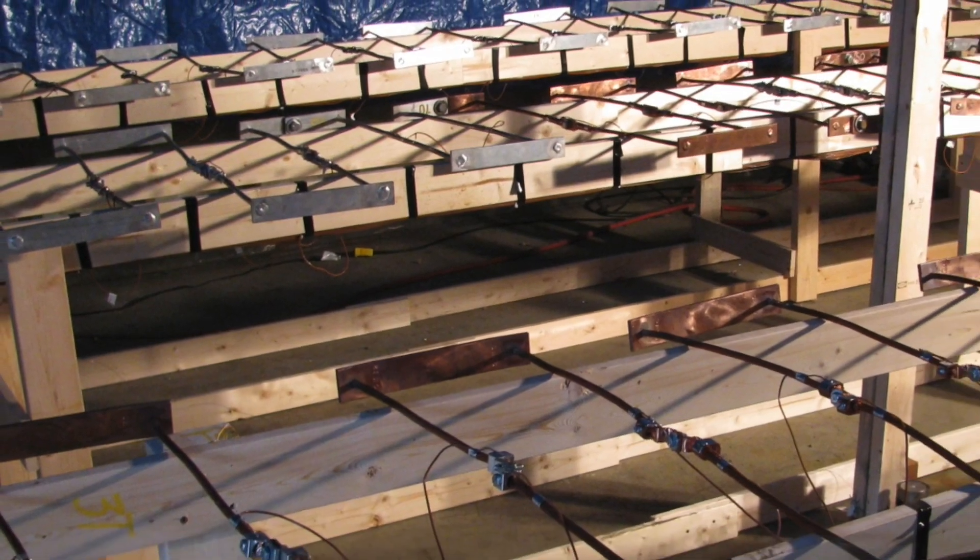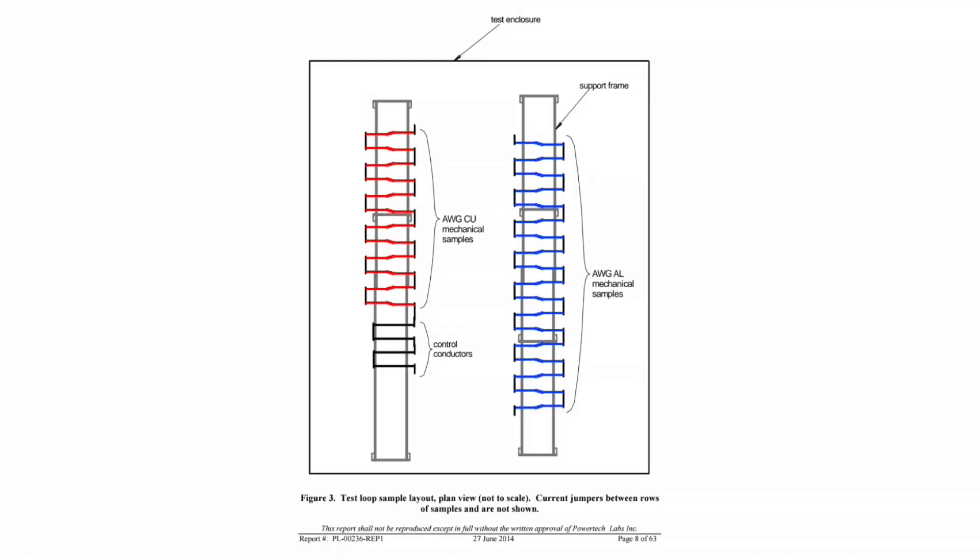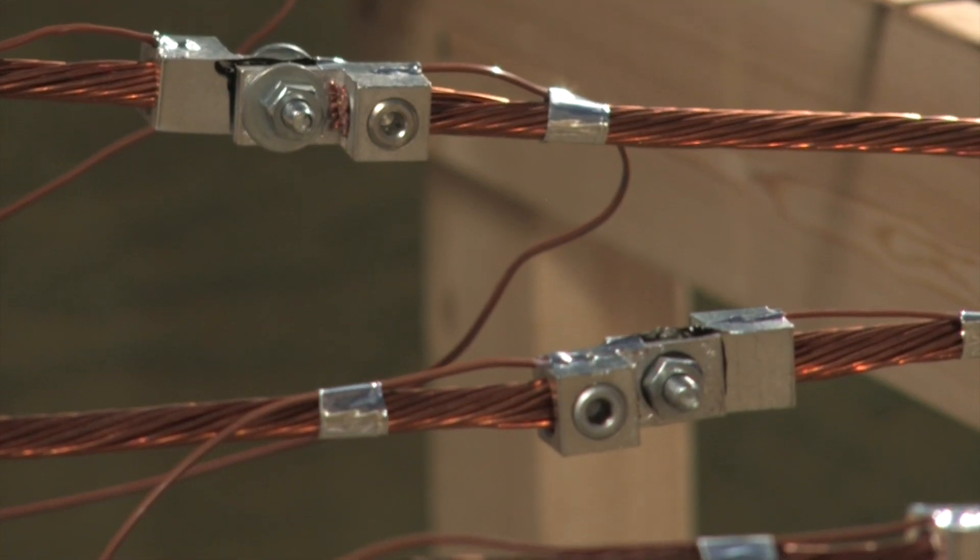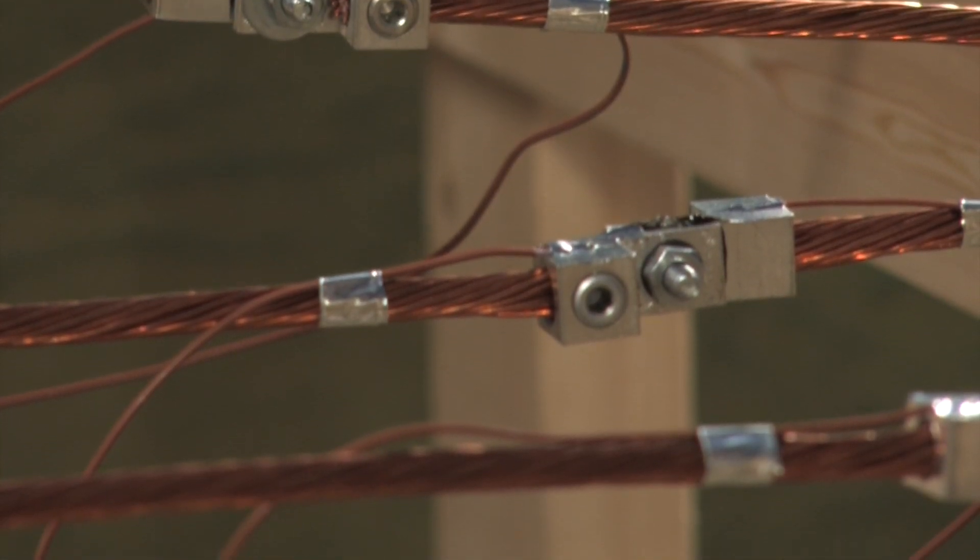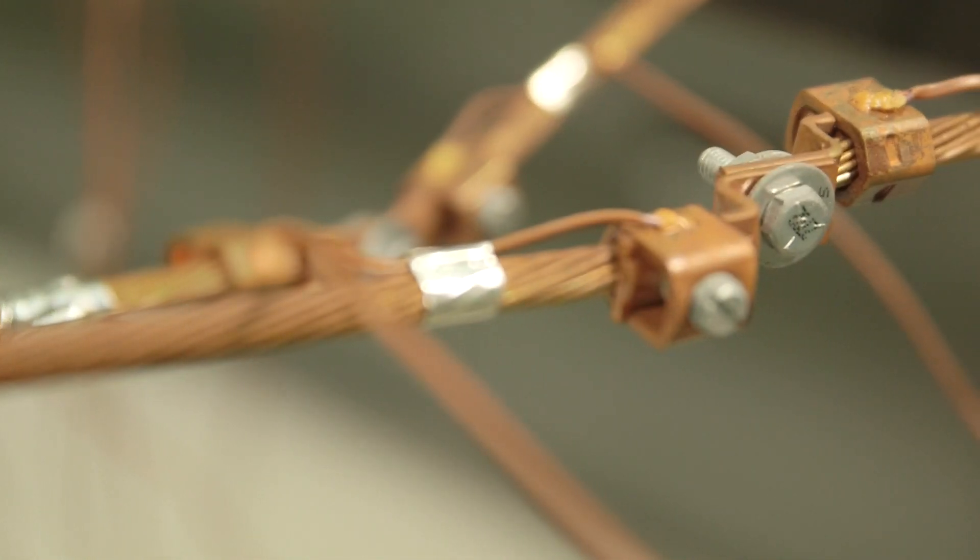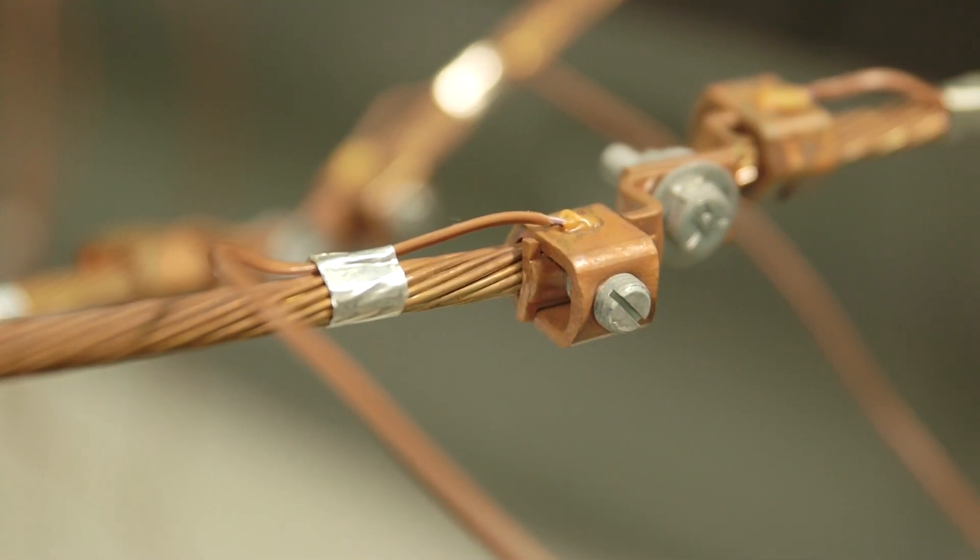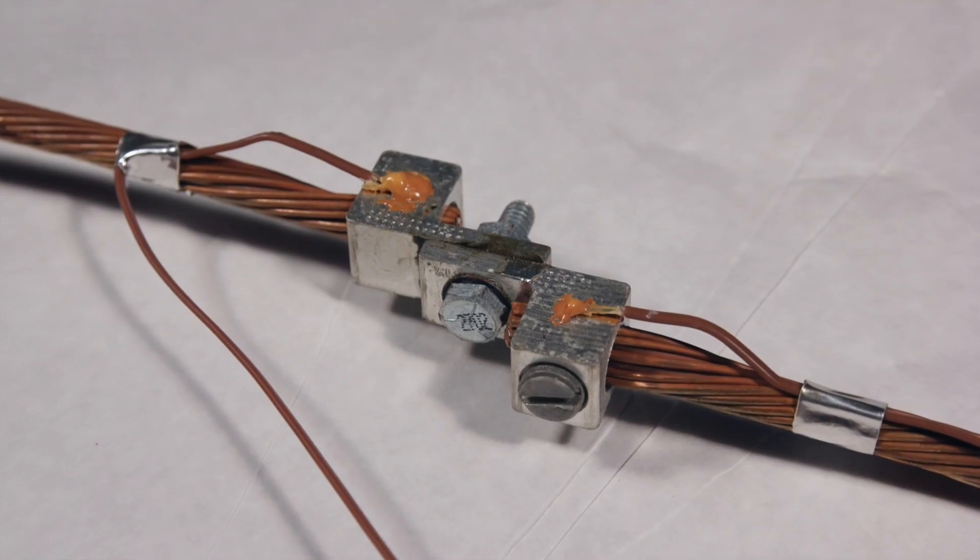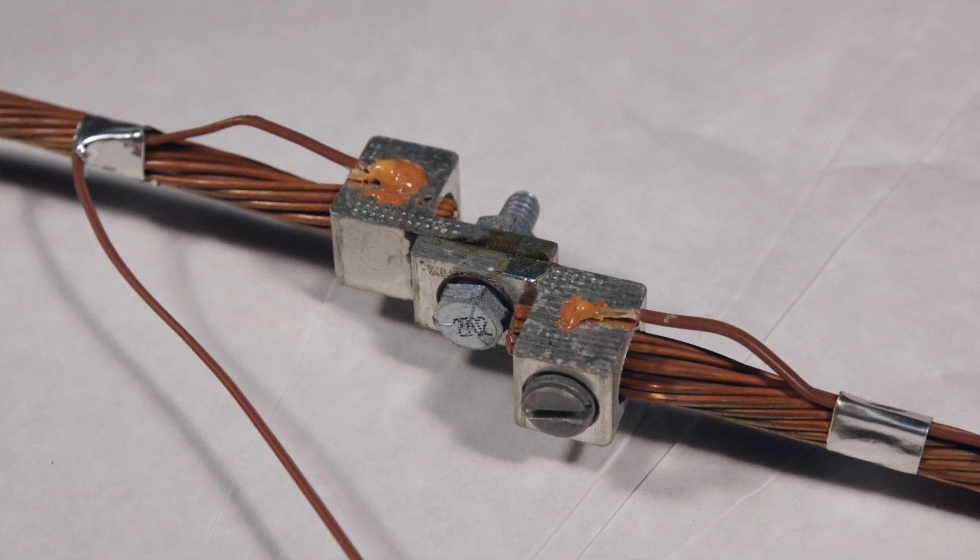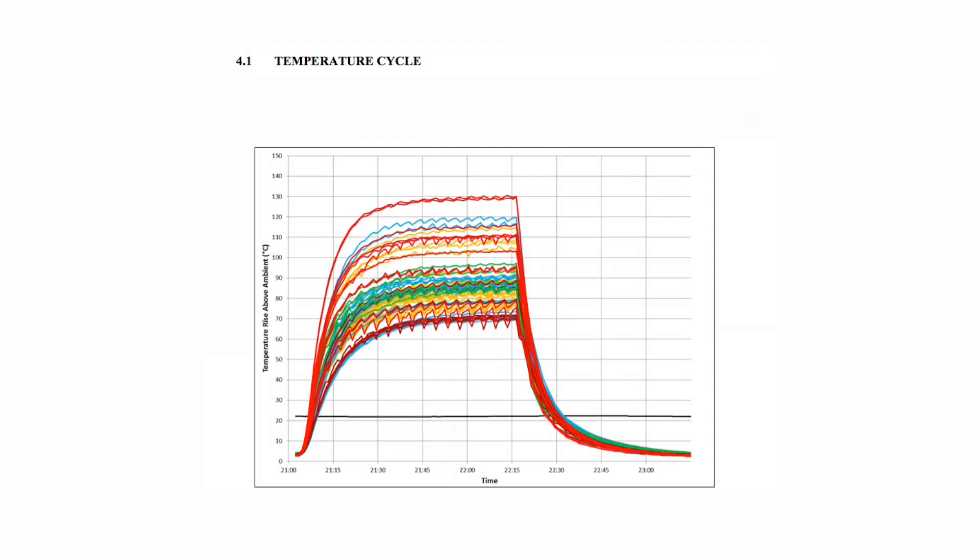The test samples were connected together in a series circuit as shown in the diagram so the same current level could be passed through all samples simultaneously. During testing, the current was automatically regulated at a fixed level and the temperature of each connection was measured using thermocouples. Each current cycle was two and a quarter hours long and consisted of heating the samples to temperature stability at a constant current level followed by a cooling period back to room temperature. A total of 1500 current cycles were performed for the test.